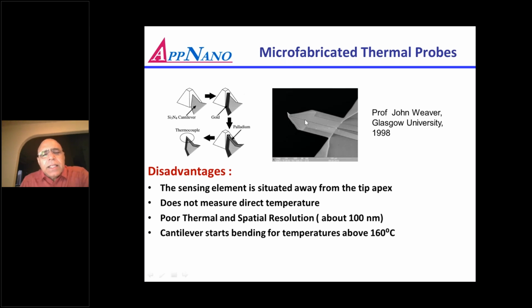These probes are basically silicon nitride. If you see this image, there is a silicon nitride cantilever, and the metal is patterned on top of this to make a thermocouple. So what they do is make a pyramid, and on this pyramid the silicon nitride cantilever is patterned. One of the problems with this technology is that, since the lithography is on a pyramid, it has to be done with e-beam lithography. This probe requires at least 4 or 5 steps of e-beam lithography, and that makes it very difficult to make in a simple microfabrication factory. So after patterning the silicon nitride cantilever, the two metals are coated, and eventually you get this palladium gold thermocouple over here at the end.